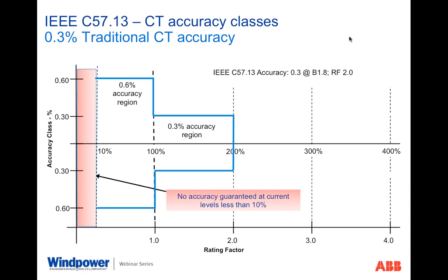And as you see here, a 0.3 class device really starts getting inaccurate as you go lower and lower in the current level. At 100%, you're in the 0.3 class. Down at 10%, you're in the 0.6% accuracy class potentially. And below that level, nothing is defined. So from a metering perspective, you really want to stay up in the upper regions of that measuring range to be able to get the best accuracy and maximize your return. Unfortunately, this particular model didn't work well on the wind farm model, because in this case there was great concern to both the owner and the billing entity that you weren't being covered down at the low end, in this region down here in the pink.